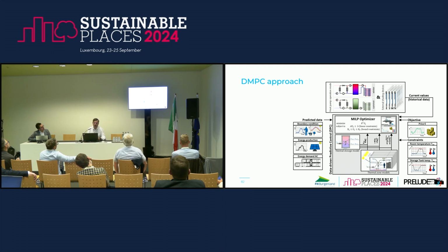We have models, we can talk about a digital twin here, to describe the thermal behavior of the thermal zones and also of our storage tank. The storage tank is in the summer months the cold water storage tank, and in the winter months the hot water storage tank. So for numeric optimization we can only operate in one way, either the winter or the summer operation mode. We also need a weather forecast. We need a model of our PV system to make a forecast about the yield of the PV system. We can make a forecast about the internal loads with the historical data, and we also need the energy demand of our air handling unit. So how much energy the preheater or the cooling unit needs for the next forecast horizon, for example, the next day or 24 hours.